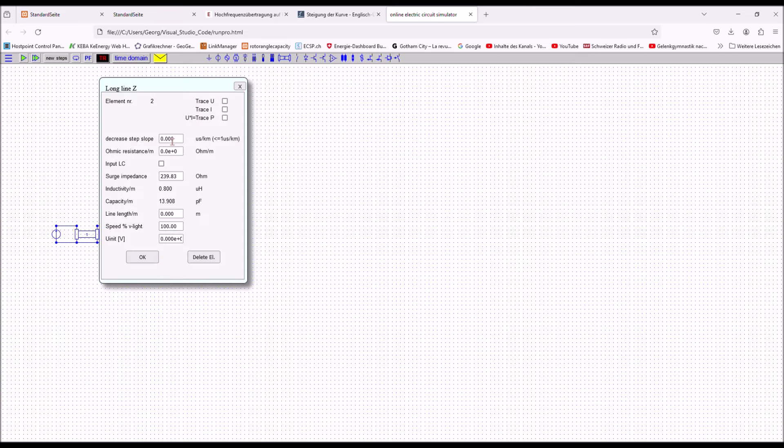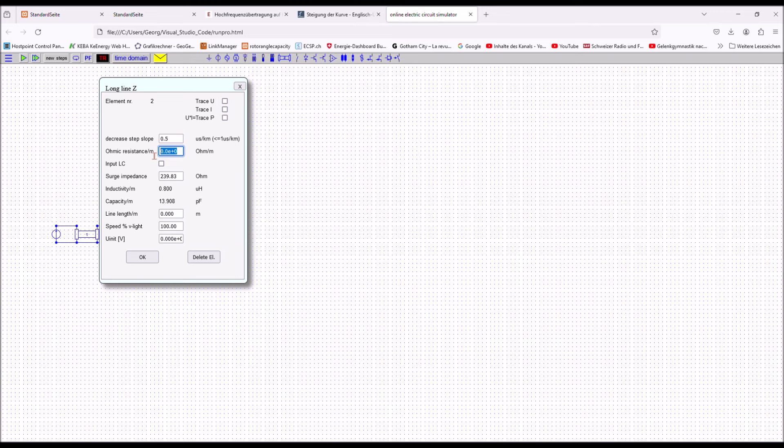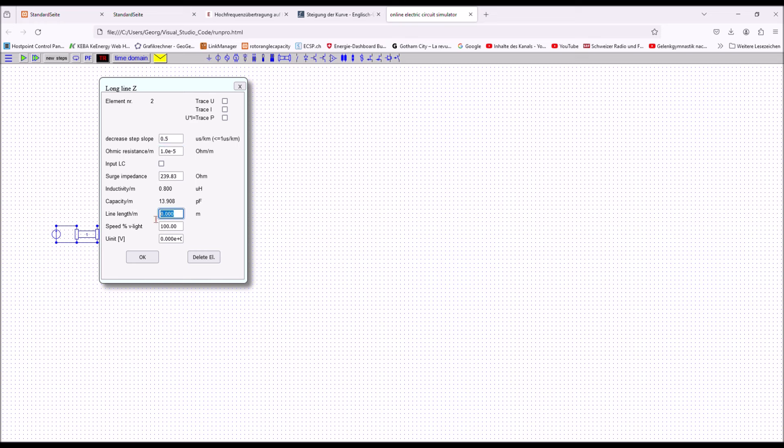Double click now on the line element to open the line input form. Enter the damping in microsecond per kilometer. This means that the slope of a surge is decreased by so many microseconds per kilometer. With input zero, there is no damping for the slope at all. Enter the length resistance of the line in ohm per meter. Realistic is something around 10 micro ohm per meter. Enter the surge impedance, the length of the line in meter, and the traveling speed of a surge in percent of the speed of light. 100 is normally good enough for an overhead line.